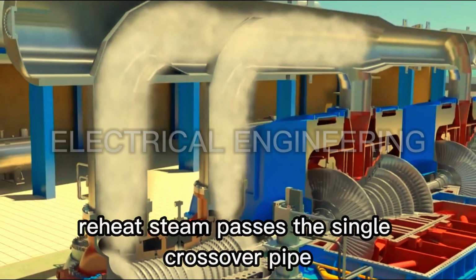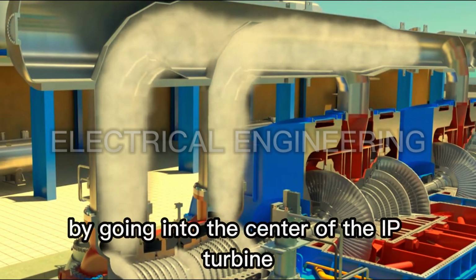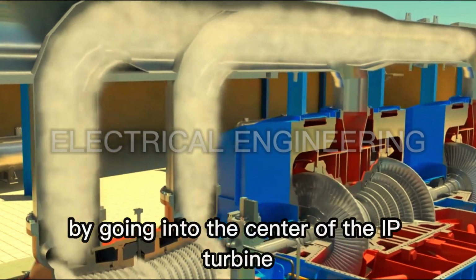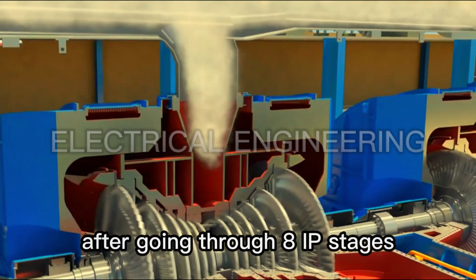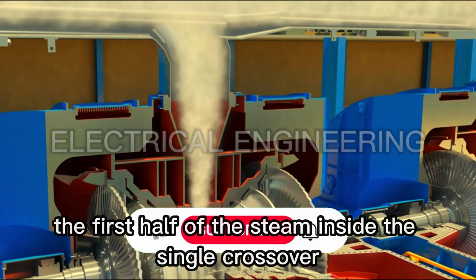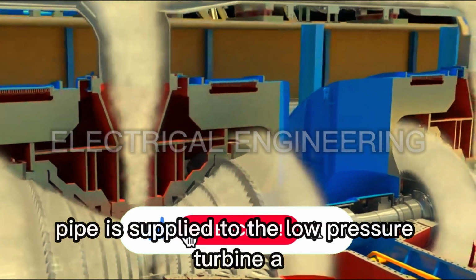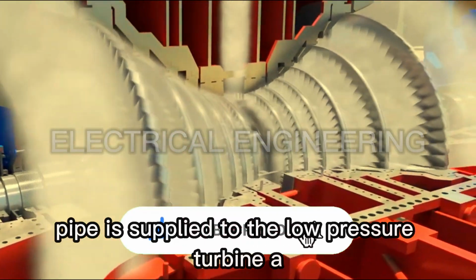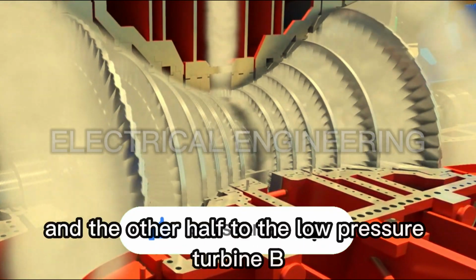Reheat steam passes the single crossover pipe by going into the center of the IP turbine after going through 8 IP stages. The first half of the steam inside the single crossover pipe is supplied to the low-pressure turbine A, and the other half to the low-pressure turbine B.